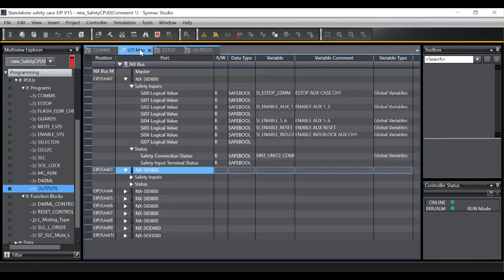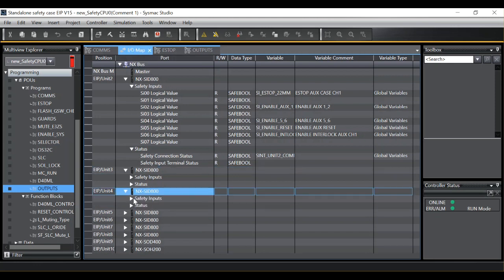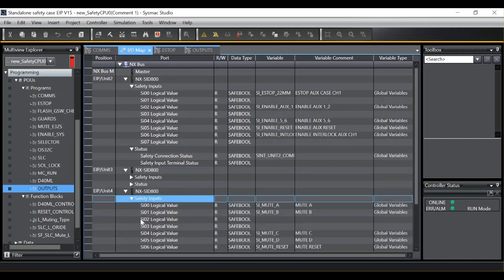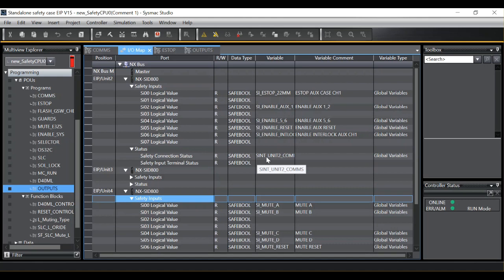Within SysMAC Studio if you move to the IO map you can see my various safety inputs here and all the slices. Under the status section you will actually see we get a safety connection status variable that we can associate. So we can type in a variable name here. I've used SINT to stand for safety internal unit 2 comms.